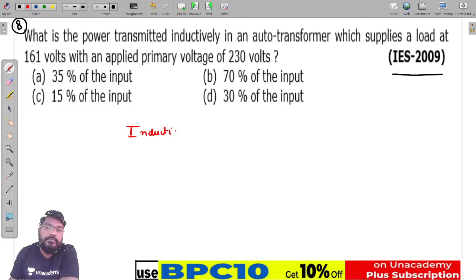Okay, this is the formula. Where k is equal to the transformation ratio of auto transformer, that is low voltage of auto transformer divided by high voltage of the auto transformer. Here it's 161 divided by 230 volts. Now substitute into the induction kVA formula: induction power of auto transformer equals 1 minus 161 divided by 230, multiplied by the input kVA.